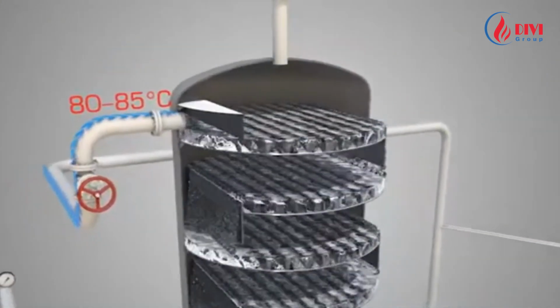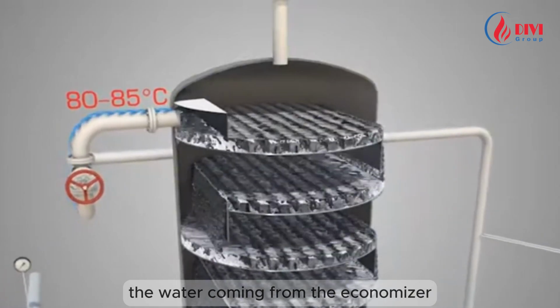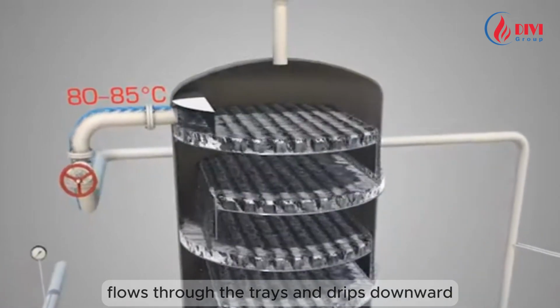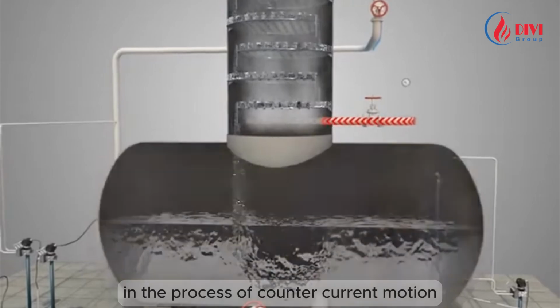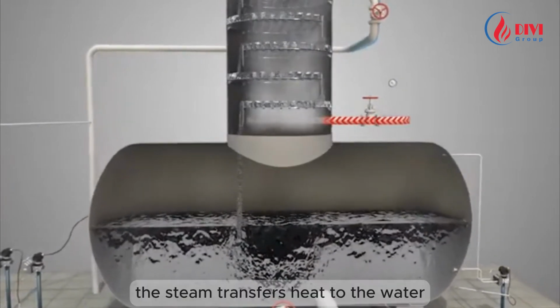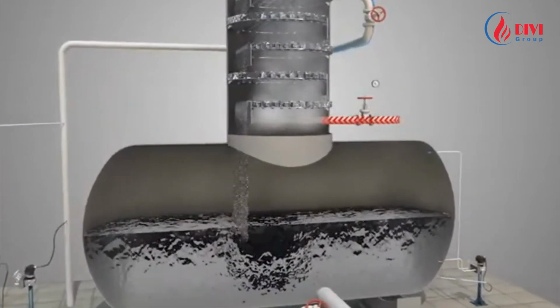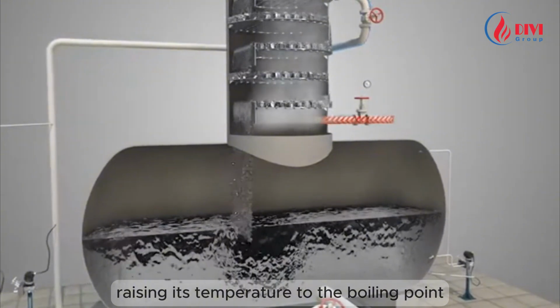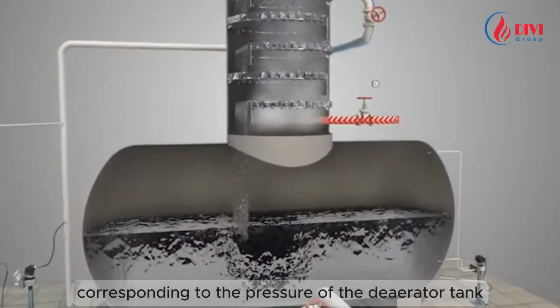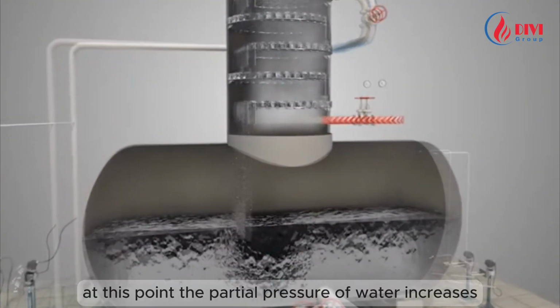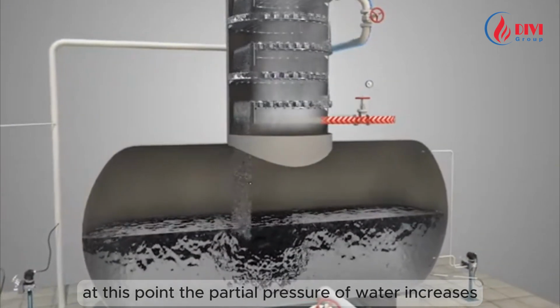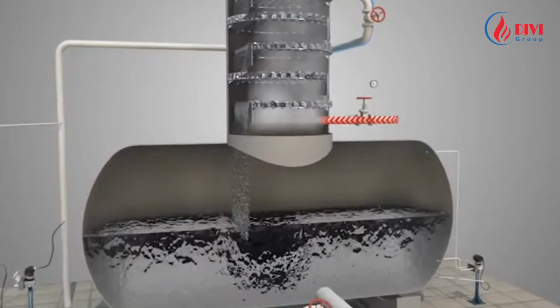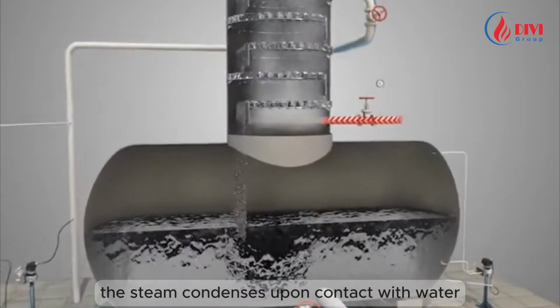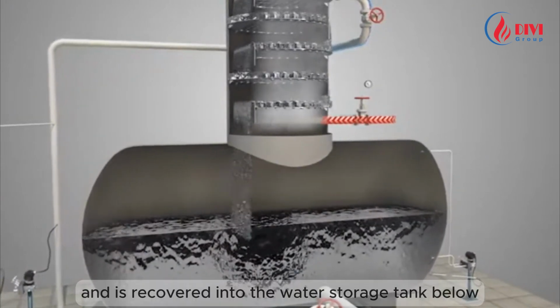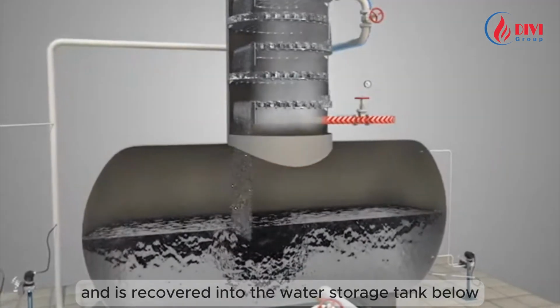At this point, the water coming from the economizer flows through the trays and drips downward. In the process of countercurrent motion, the steam transfers heat to the water, raising its temperature to the boiling point corresponding to the pressure of the Deaerator tank. At this point, the partial pressure of water increases. The steam condenses upon contact with water and is recovered into the water storage tank below.